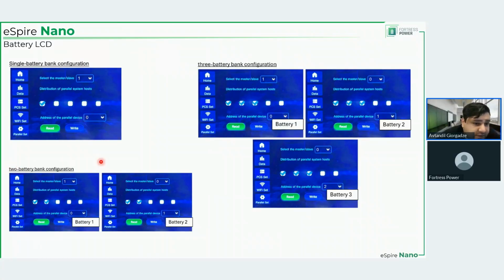For a 2 battery configuration, on both batteries, you have 2 check marks, right? First 2 slots are check marked on both, but battery 1 has the role of a primary or master battery. Battery 2 has the role of the following one. Address of the parallel device, you tell battery number 1 that, hey, we start counting from you, and you tell battery number 2, you're the first compared to 0. So 0 and 1. For a 3 battery configuration, obviously the logic remains the same. It's just that instead of 2, you're going to have 3 check marks on each. You will have 1 primary or master battery. You will have 2 secondary or following or slave ones. And on the second one, you will have address of parallel device 1. And on the third one, you will have address of parallel device 2.